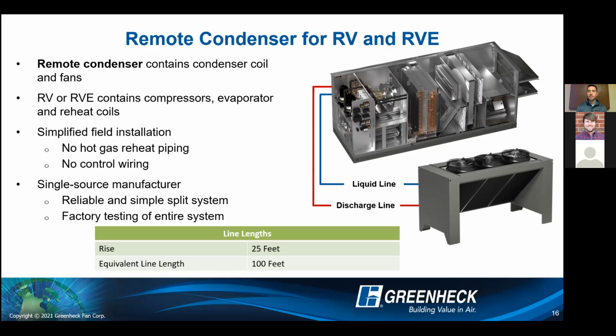Typical rise is going to be about a 2-story building, so 25 feet of rise. Doesn't matter if the condensing section is on top or basically above or below the actual RVE unit. And then the equivalent line length is about 100 feet right now. So that includes the rise, any sort of elbows or T's that you do have. And there are certain situations when we could potentially go above these line lengths. So if you do have an application that's a little bit higher or maybe a little bit longer from an equivalent line length standpoint, reach out to Holden and we'll definitely work with you on that split system application to see if there's any concern.